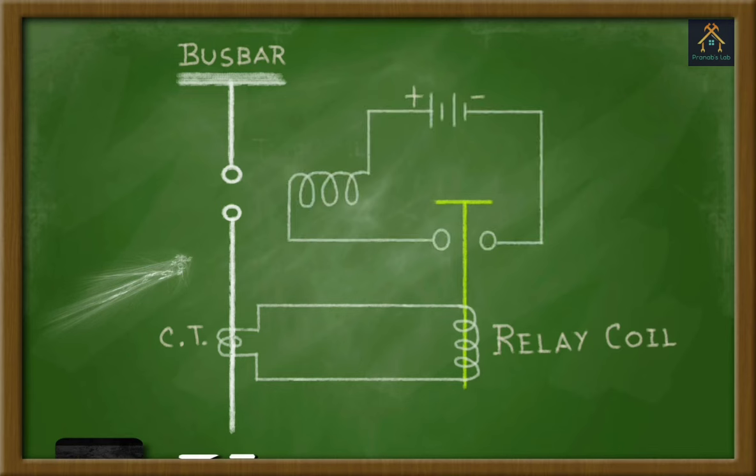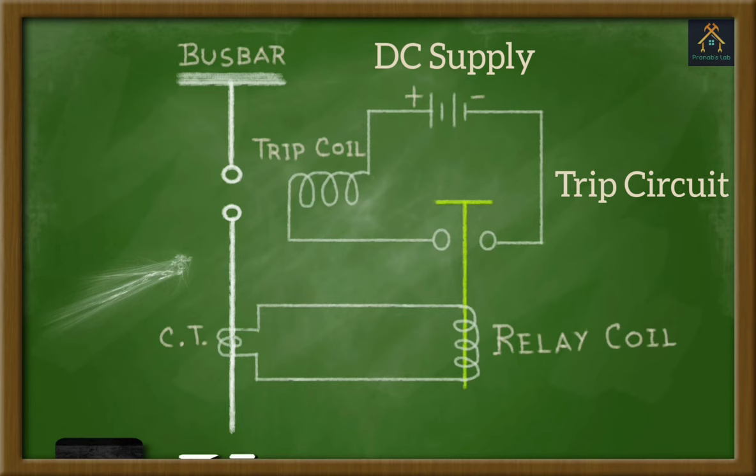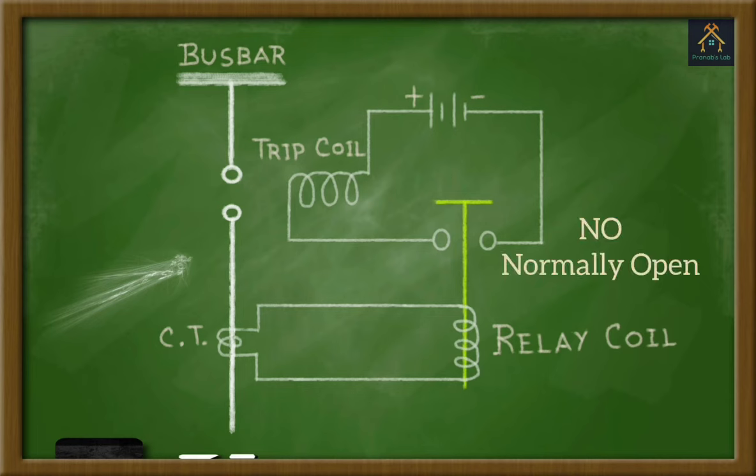Now, you can see a separate circuit is drawn just above the relay coil plunger. This circuit is called the trip circuit. The circuit contains a DC power supply from battery, a trip coil and two contacts. The contacts are placed just below the relay coil plunger. The trip circuit can be closed only by the relay coil plunger. Please remember that the trip circuit contacts are normally in open condition.